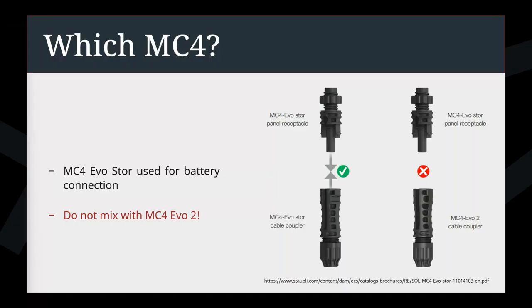So generally speaking, if you mix connector types, that can lead to contact resistance. That extra resistance can lead to overheating, which could lead to melted housings and potentially more serious damage. But yeah, you really have to be forcing it in there if you're trying to mix these two connection types, MC4 Evo Stor and say one of the other ones. So, but yeah, just a reminder, please don't do that.